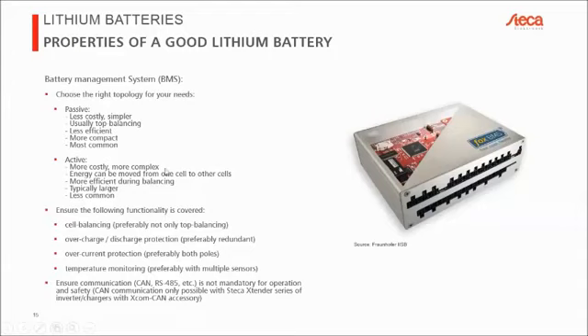Then there's the active BMS, which is the higher end one, more costly and more complex. Instead of wasting energy as heat when cells are full, it can take energy from a cell that's too full and give it to a cell that's not full enough. This increases efficiency during balancing, but it also means much more complex electronics, a larger BMS, and therefore it's less common. This doesn't make it safer though—the safety of a BMS really depends on the manufacturer, the software, and the hardware used. You can't say an active BMS is safer than a passive one.